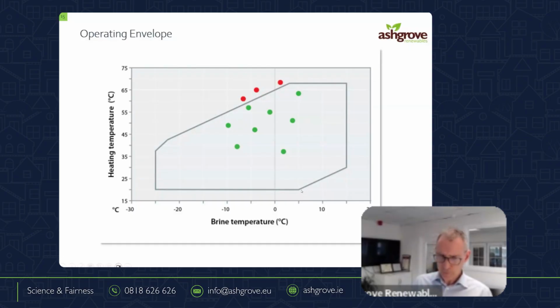But so you can see here, in this case, if I drop the brine temperature, so the temperature from the ground is dropping, I'm taking too much energy out of the ground. I haven't put in enough pipe work or whatever is wrong. I, number one, can't get the heat pump to operate to the temperatures maybe above, in this case, 45 degrees I've just shown there. As the air temperatures get higher or the brine temperatures get higher, I can, I suppose, get increasingly higher flow temperatures on the condensing side. But all gases will have their maximum. In this case, it is showing whatever that is, 67 or whatever. But once it comes up here, we start going into what's known as high pressure alarms and the various instability issues with the gas. But they'll all have an envelope. It doesn't really matter what temperatures it's occurring at or anything else, but that's the envelope that we're happy in. If we go outside of that, the heat pump is going to have problems.